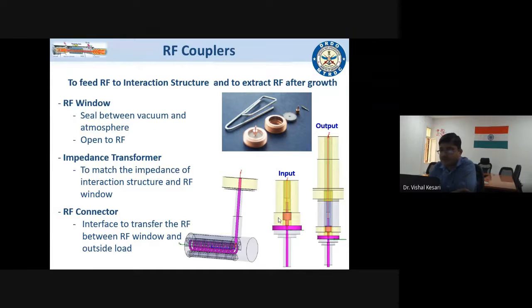Then further, coming to the input output coupler, the coupler is also a very critical assembly. See, inside the tube you need to maintain the vacuum, however outside there is atmosphere. So we want a seal so that atmosphere does not enter the device. However, from the same path we want RF to come out. So at one end we want to stop the atmosphere and let RF come out. It should be a good seal for vacuum and atmosphere, and it should be open for RF.